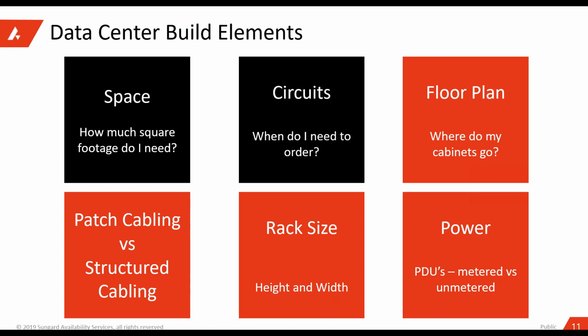Circuits. When do I need to order them? If you're thinking about a move, say Q1 of 2020, you need to order today or by October 1st. Normal installation for circuit runs is anywhere from 60 to 120 days, probably worst case. You want to get your circuit in and do at least minimal testing and validation before. Once it gets dropped by the telco, you're going to need cross connections from the DMARC to your cabinet.